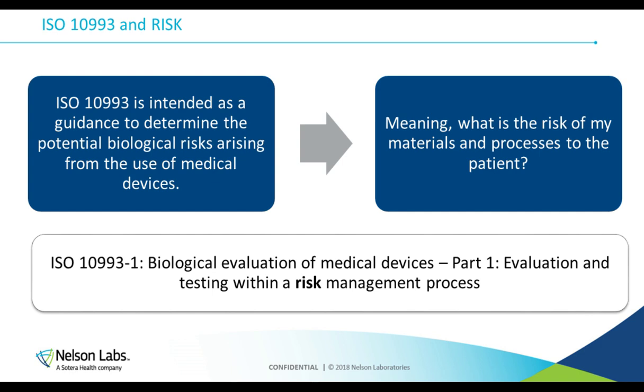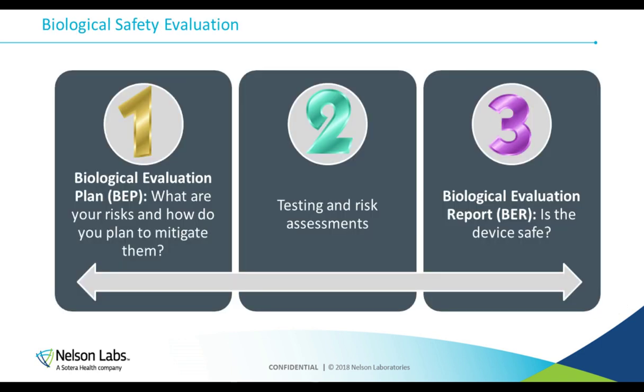ISO 10993 makes this very clear. It says that it is the evaluation and testing within a risk management process. So that's absolutely central to your submission and becoming compliant with the MDRs: that you've taken a look at your device and its inherent risks, you've understood what the risks are, and you have a clear plan and path to address and mitigate those risks.